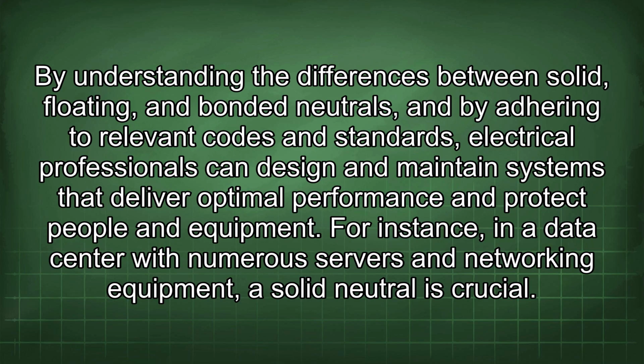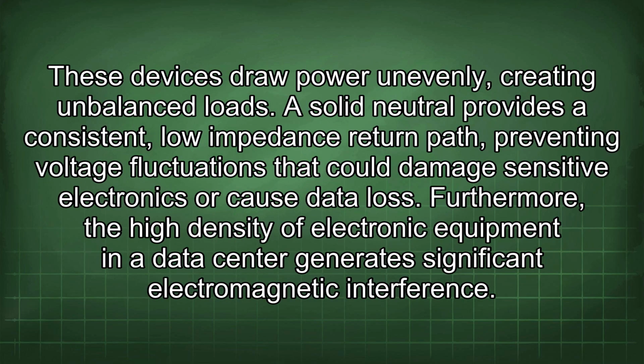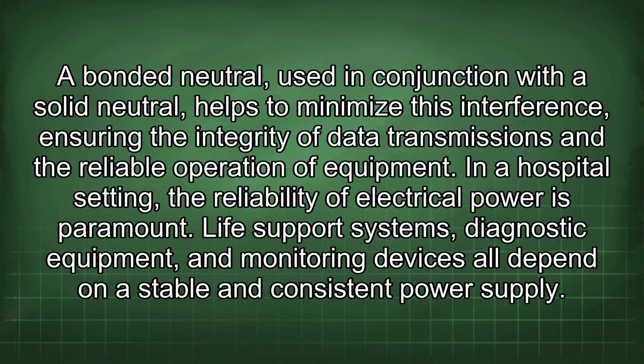For instance, in a data center with numerous servers and networking equipment, a solid neutral is crucial. These devices draw power unevenly, creating unbalanced loads. A solid neutral provides a consistent low-impedance return path, preventing voltage fluctuations that could damage sensitive electronics or cause data loss. Furthermore, the high density of electronic equipment in a data center generates significant electromagnetic interference. A bonded neutral, used in conjunction with a solid neutral, helps to minimize this interference, ensuring the integrity of data transmissions and the reliable operation of equipment.